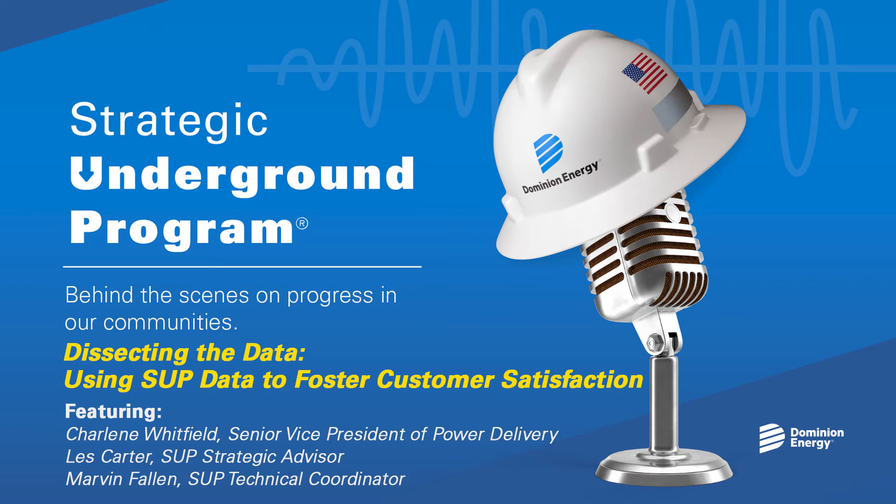Great point, Charlene. Thank you for sharing. Marvin, I'm going to turn to you now as a technical coordinator for the program. You're the one who's in the field scoping proposed areas for undergrounding. How do you rely on the data to help you make the right decisions? The data we use for scoping proposed areas for underground is very in-depth. It shows outages that have happened in the last 10 years, the lengths of taps, where the taps are located — organized by county and city — and also the customer count. I'm able to use this data to do two important things. One, sort by the customers per mile of line so I can determine whether a project will affect a significant number of customers given the outage history. Second, the data helps me to see the outages per mile of line, helping me to determine how many outages are happening per mile.